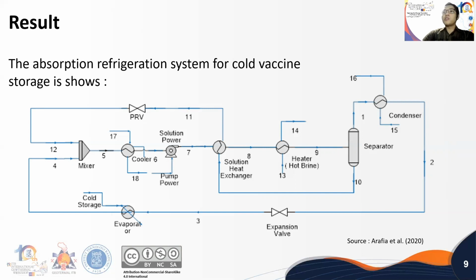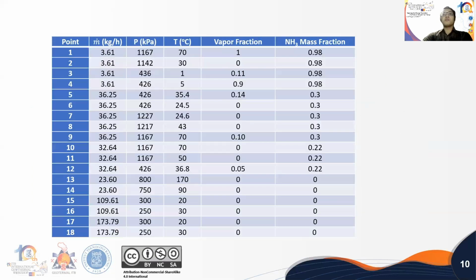This mixture in flow 5 still contains steam, so that as a condition for entering the pump, this mixture must be entirely liquid. So it must be cooled first with a cooler, so that the entire mixture is liquid in flow 6. After the mixture is completely liquid, the strong solution absorbs the heat from the heat exchanger solution, so that the temperature rises in flow 8. Then it is heated and evaporated in a heater with a brine geothermal heater.